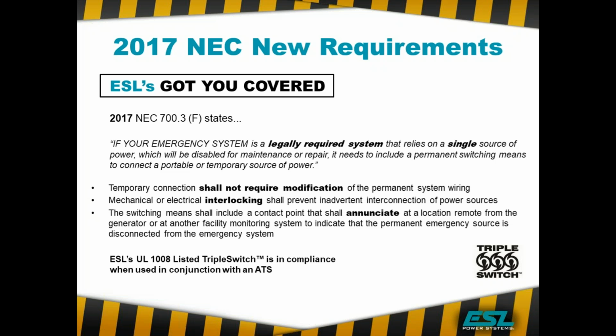If we were to use utility power, all of these requirements are standard in our triple switch when it's used in conjunction with an ATS. In addition, with our storm switch, if we add the aux contacts to it, it also then becomes compliant with NEC 2017, and we'll talk about that here in a second. So that's pretty much an overview of that. Do we have any questions on NEC 2017?